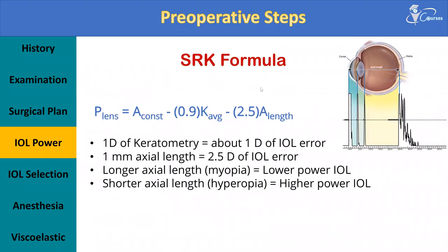So you see, this is the waveform of the A-scan. When you are putting the A-scan probe perpendicular over the surface of the cornea, there should be spikes. These spikes should be at a parallel plane, depending on your position. If these spikes are at the same level, this means that you are perpendicular over the globe.